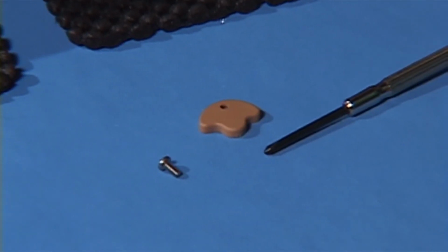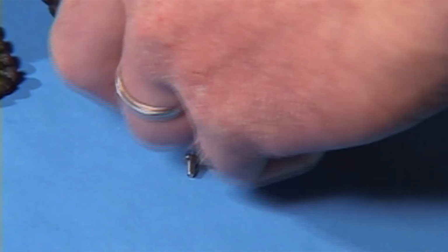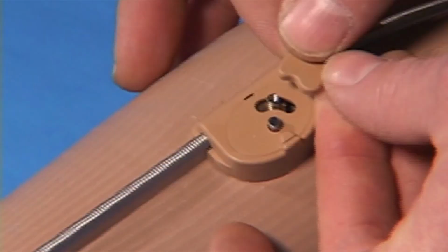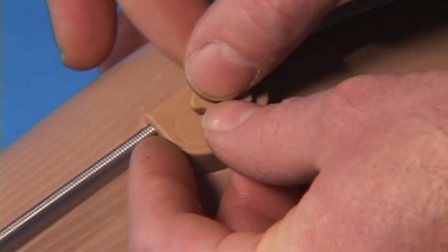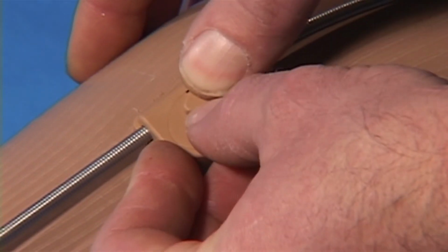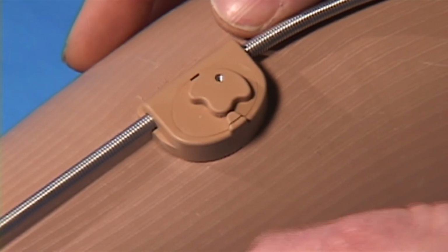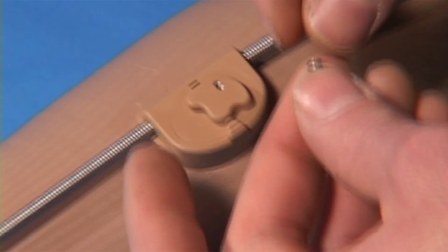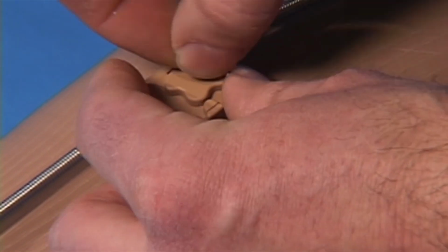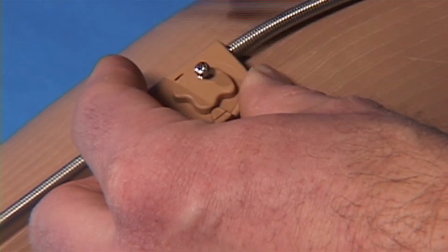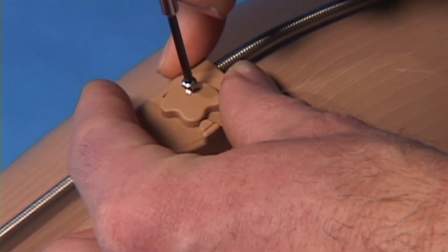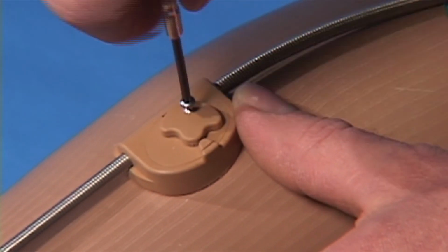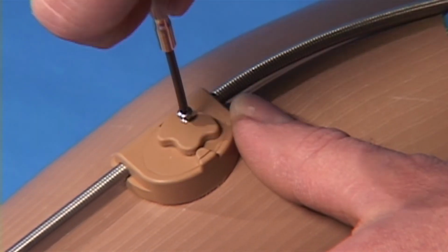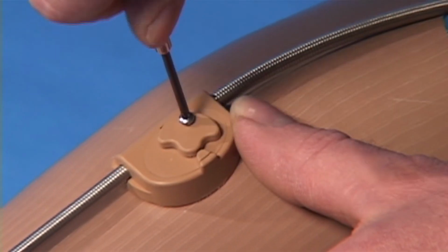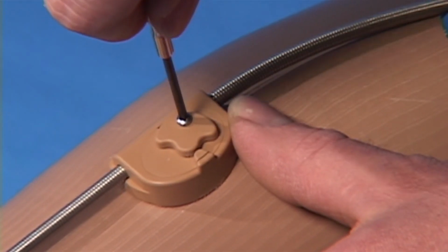Select the desired lever from the two models provided. Standard is low profile. The thicker or taller lever may be used or customized for special circumstances, for example, to meet a user's needs for locating and operating the lever. Slip the selected lever over the threaded stud and use the small fastener to secure it in place. A drop of Loctite can be used on the fastener's threads before installation. Lightly tighten the fastener. Over-tightening can distort the lever's shape and cause binding or other problems.